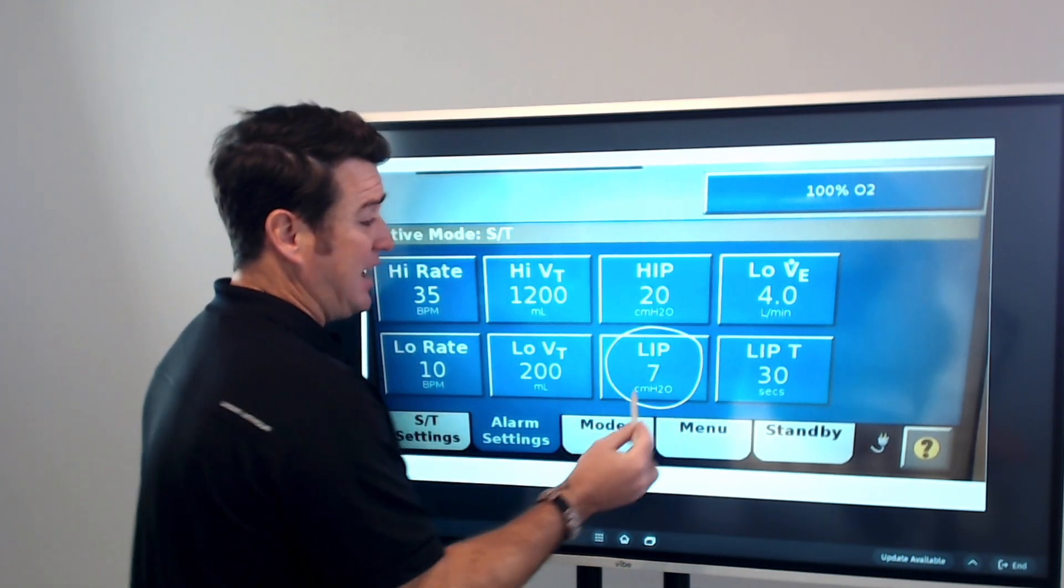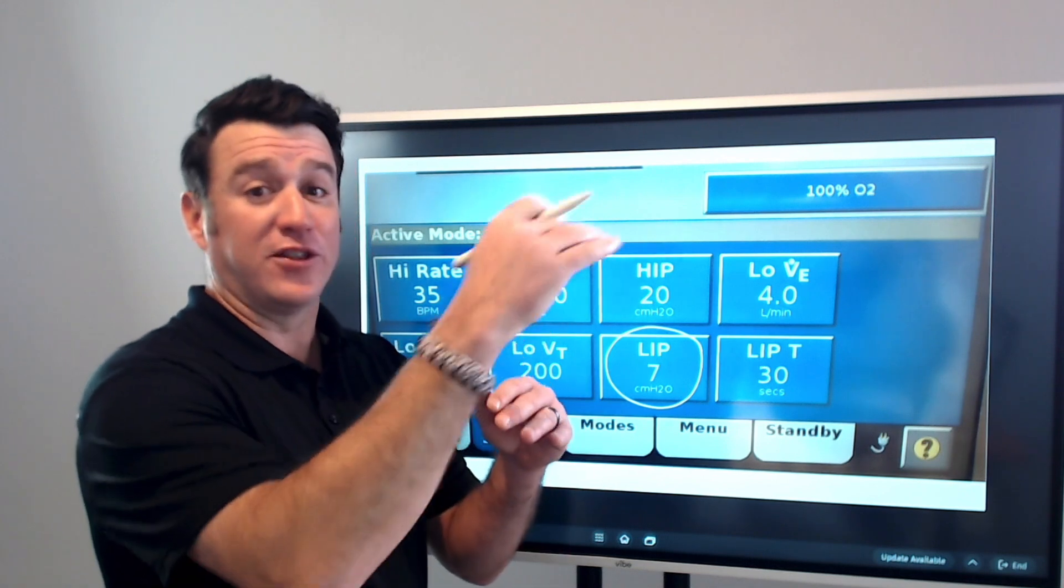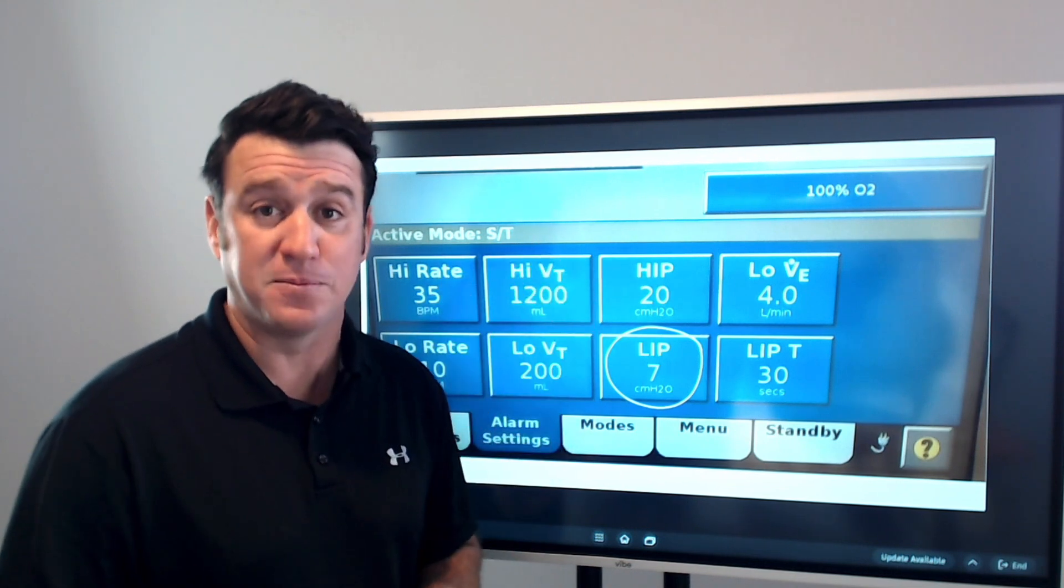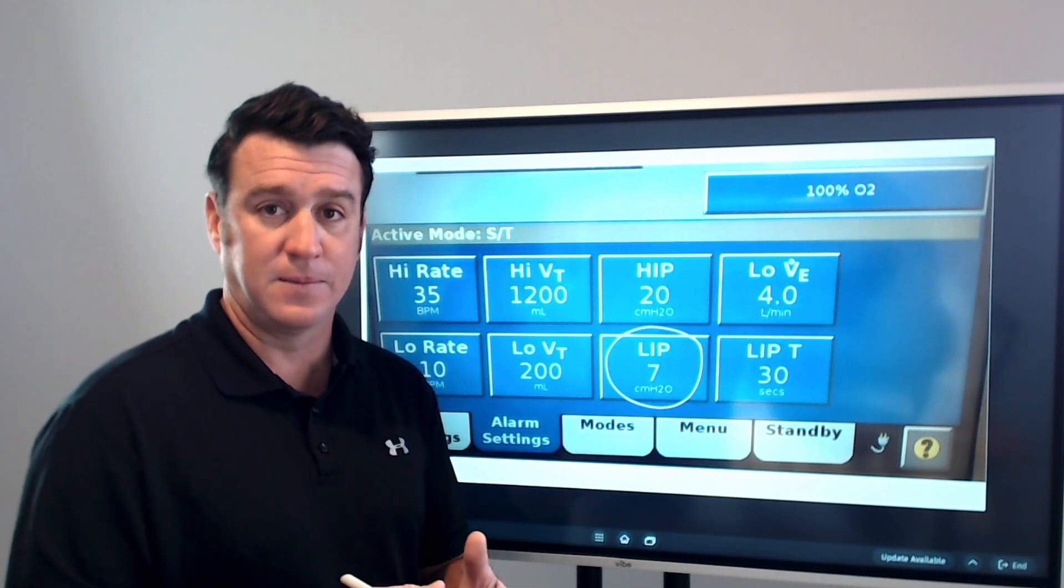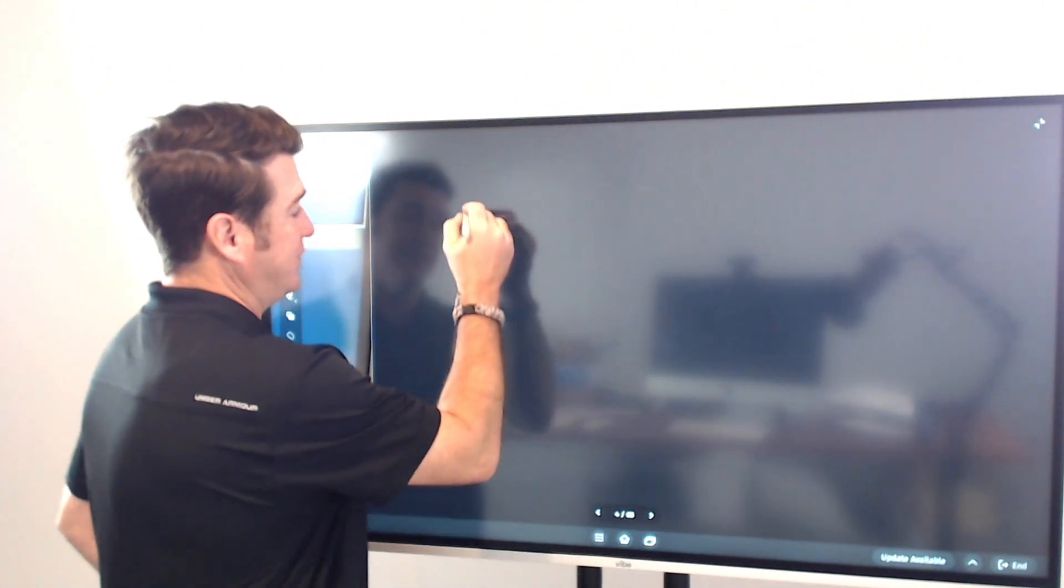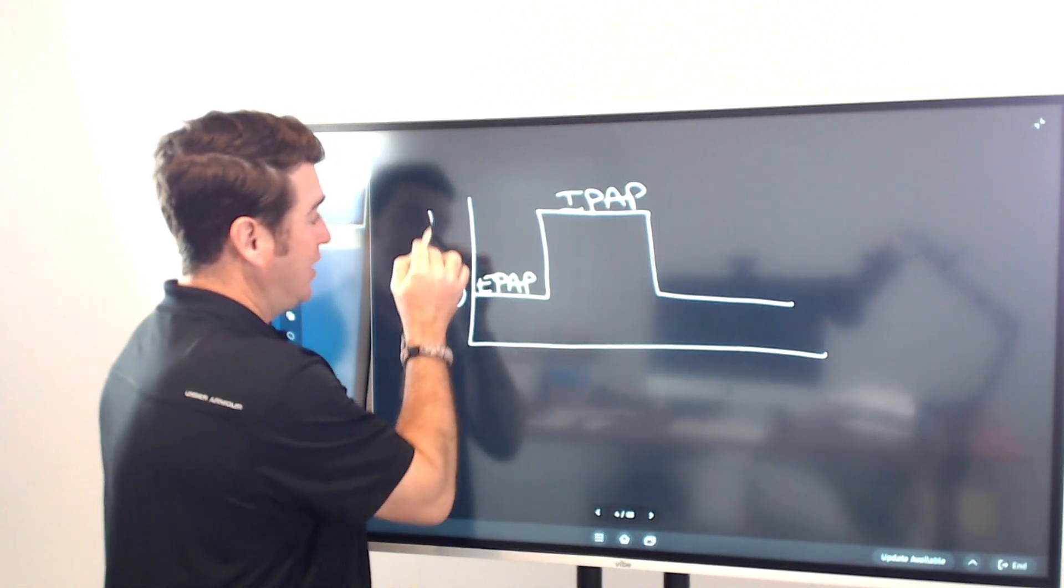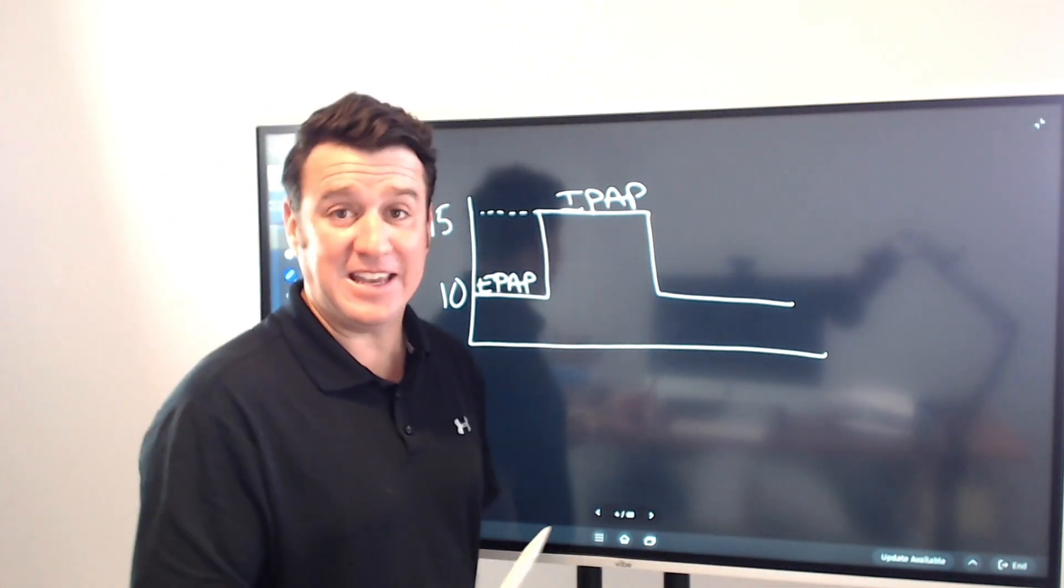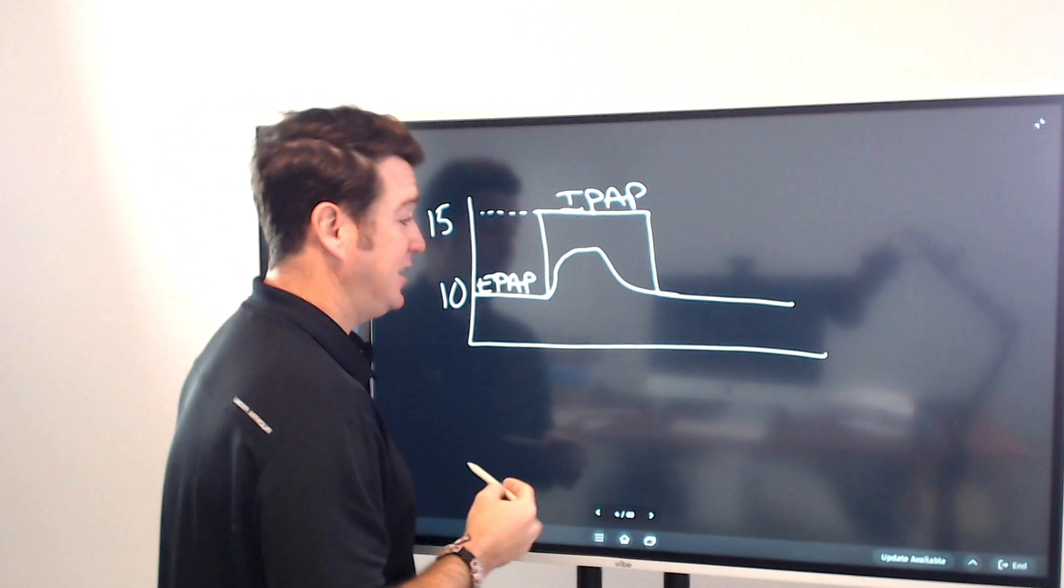Here's why. This alarm is designed to inform you if, during inspiration, you don't meet the threshold of this alarm. In other words, we're going from 10 to 15 during inspiration. So you want to be notified if an inspiratory pressure is not able to be reached. Let me give you an illustration here. If we're at 10 and raising to 15 and coming back to 10, this is EPAP, this is IPAP. Remember, we were at 10 over 15. We want to know if there is a leak in the system that is not allowing this pressure to be obtained on the inspiratory phase.